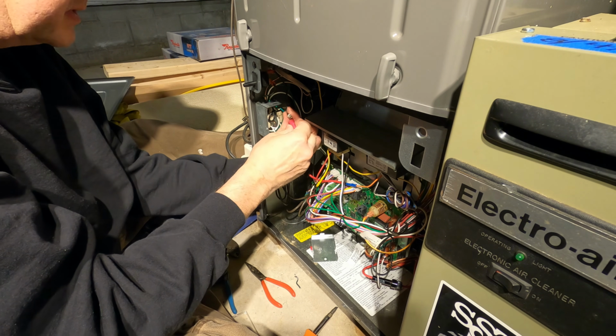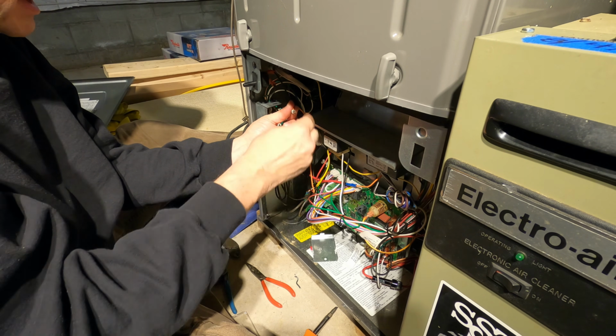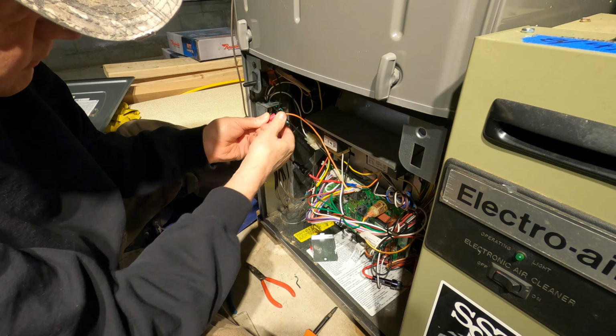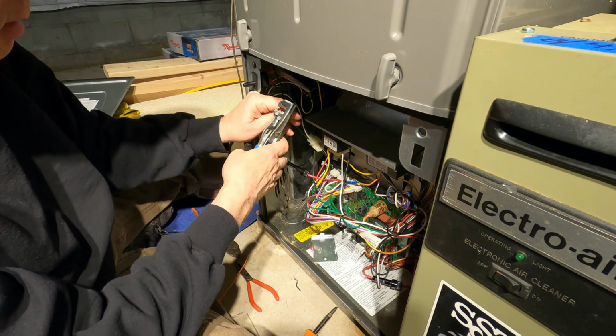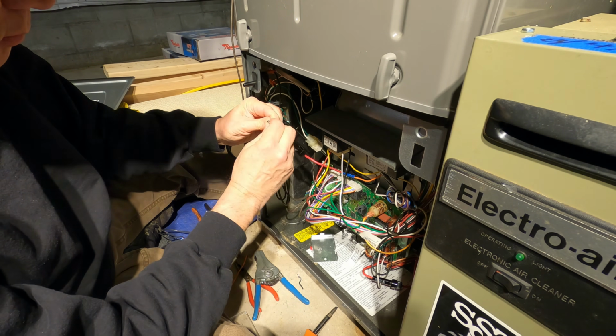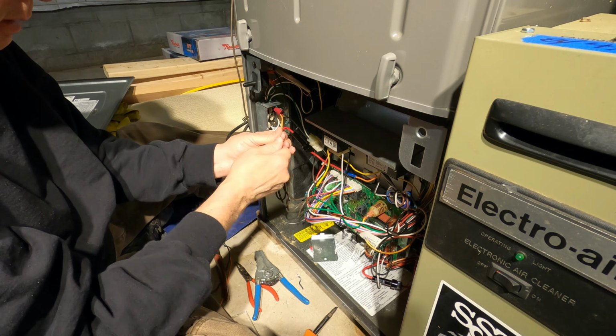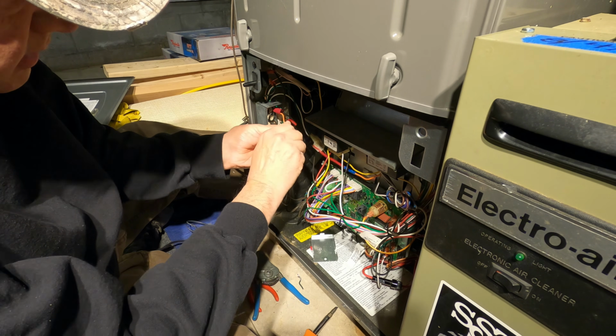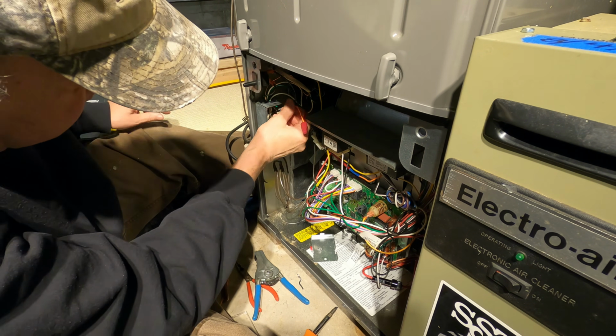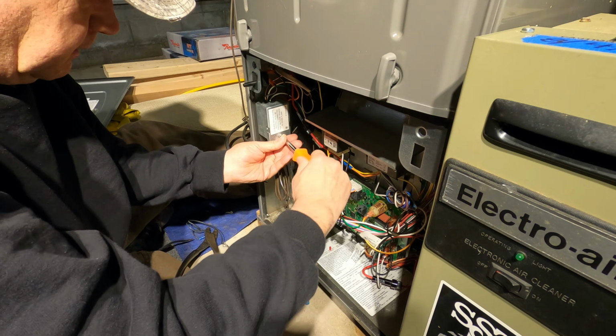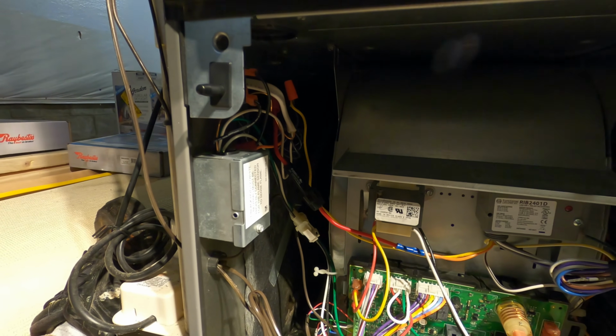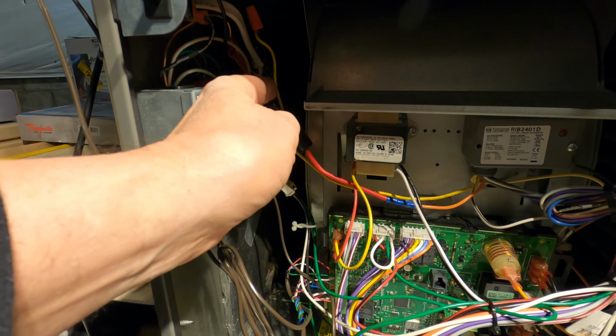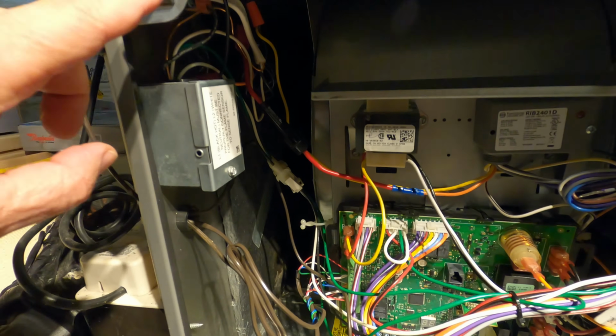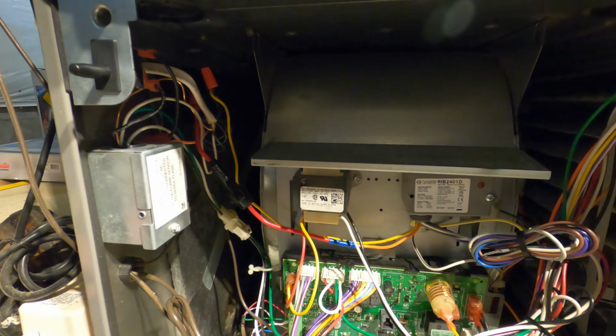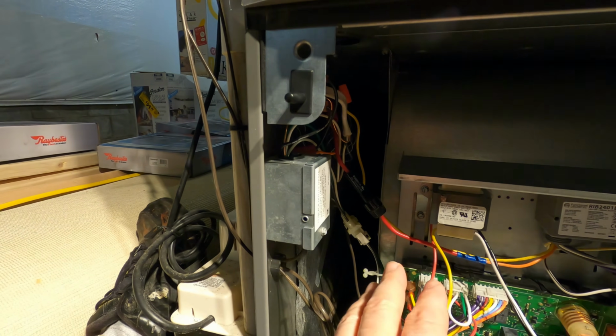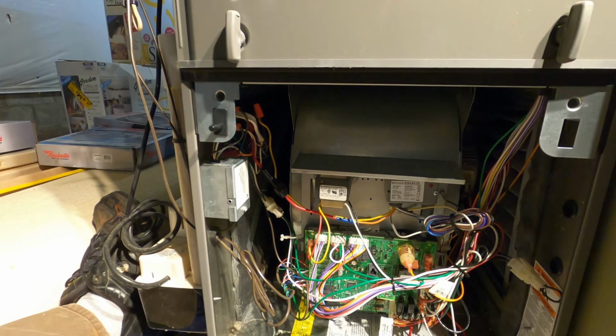I might have crimped that a bit too hard, but we'll put this cap on it, and these caps just screw on. You can feel that kind of lock on when it's screwed all the way tight. And that's that. This fused power feed to the relay gets its power through the safety switch. So now whenever this panel is removed, everything in here is dead. That makes it just that much safer.